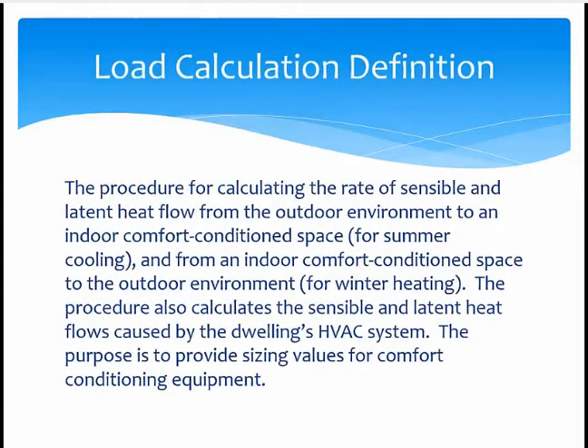What is a load calculation? Well, this is the exact definition. It is the procedure for calculating the rate of sensible and latent heat flow from the outdoor environment to an indoor comfort condition space for summer cooling, and from the indoor comfort condition space to the outdoor environment for winter heating. The process also calculates the sensible and latent heat flows caused by the dwelling HVAC system. The purpose is to provide sizing values for comfort conditioning equipment.